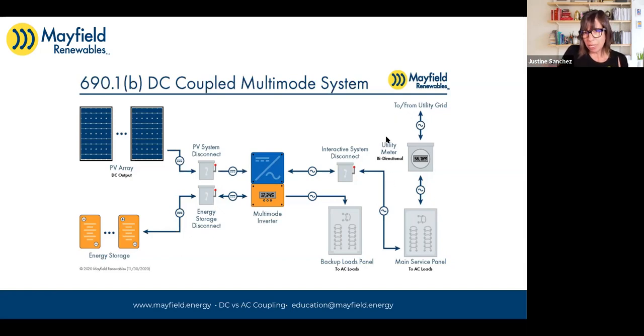But should the grid drop out, this line opens up again, just like before, with the microgrid interconnect device opening this line. We still have our powered-up backed-up loads panel that can pull power from the PV or the energy storage system, depending on the time of day and what the loads require, and where that power is actually coming from—but it has its pathway opened, and we have this backed-up loads panel.